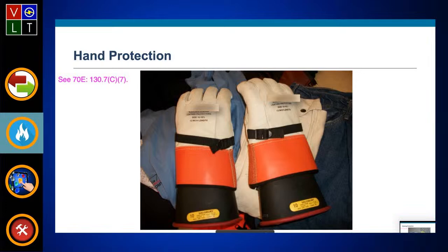All right, if nothing else, we'll go to hand protection. This is 70E 130.7(C)(7). If you look at that section, it talks about where you could use a leather glove with a liner inside, and you could even exceed 10 calories per centimeter squared, up to 12 cal on some of those gloves. In some cases you need to use leather gloves and rubber protectors, but we can find those in the tables we'll look at further into the program. This is just recognizing that you need gloves, and of course you need insulated tools in accordance with 70E 130.7(D) as in dog.